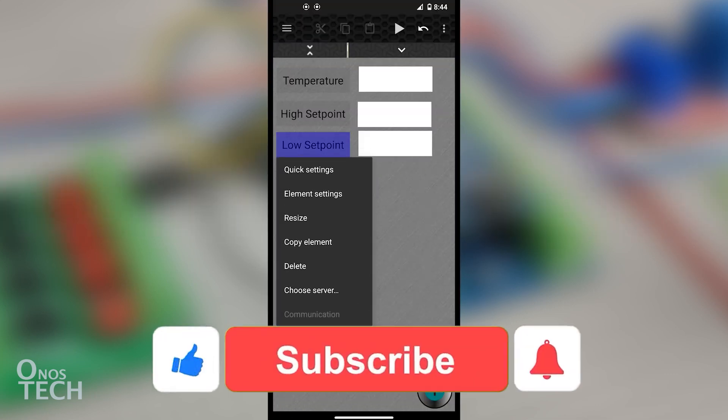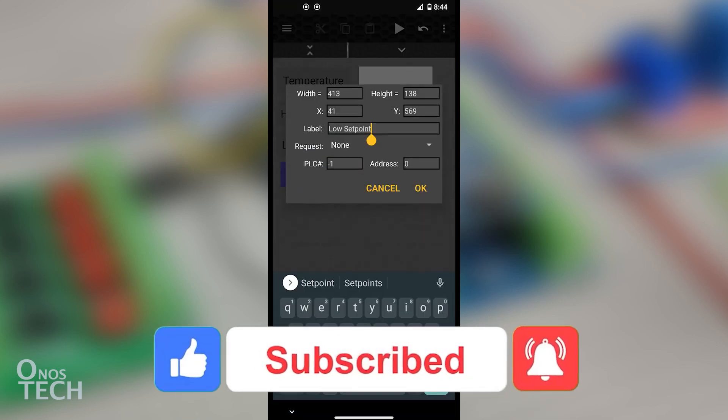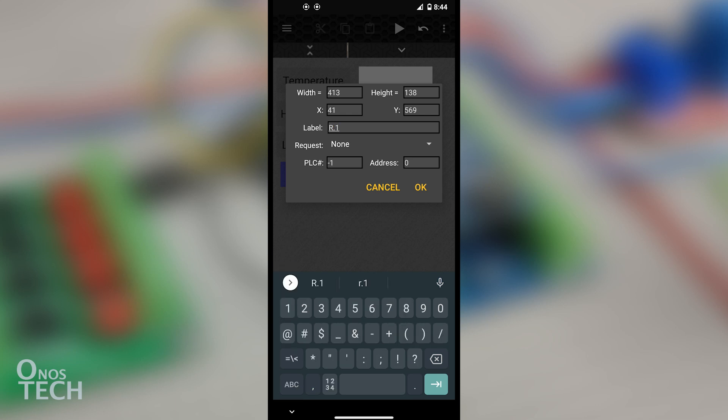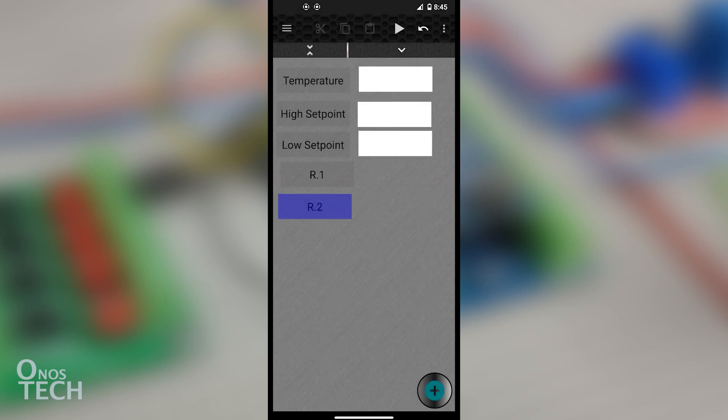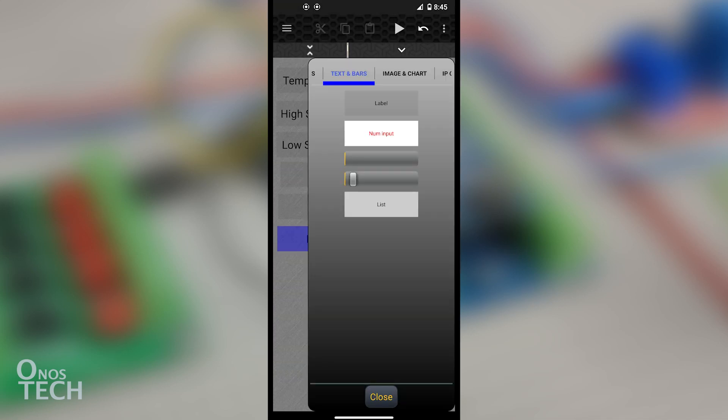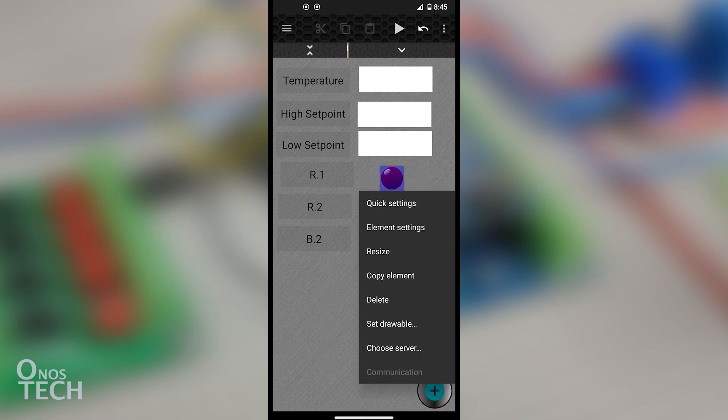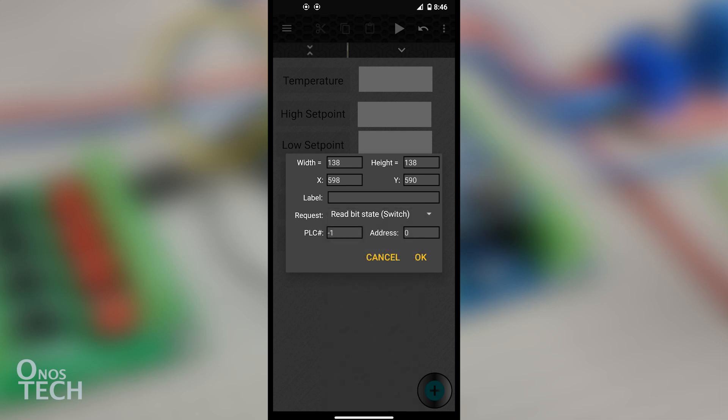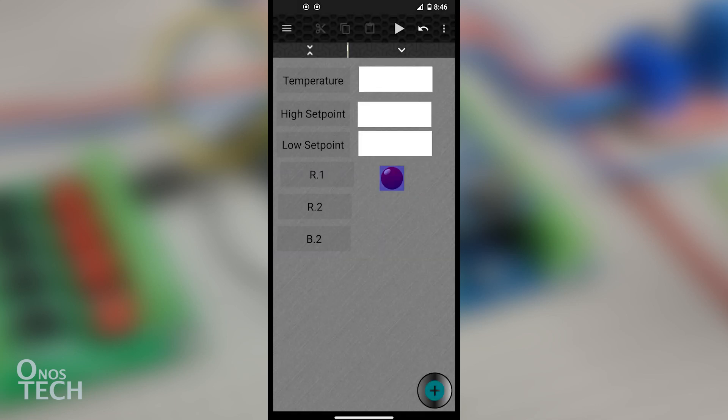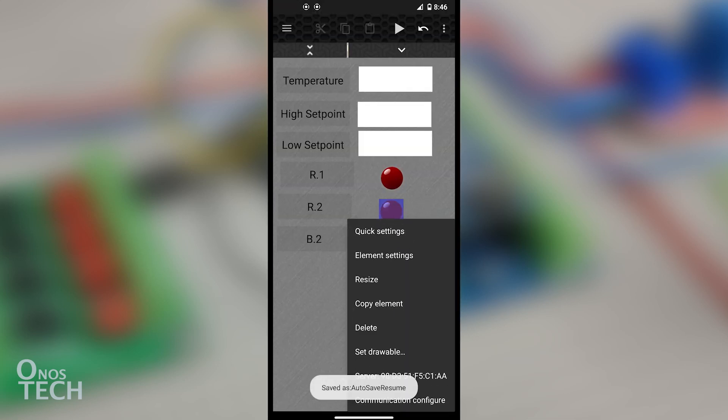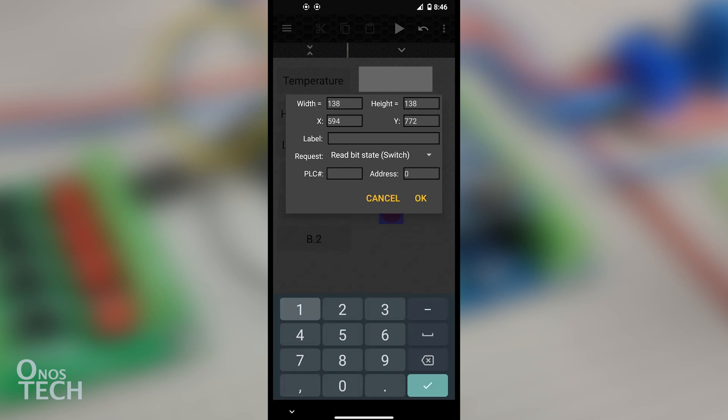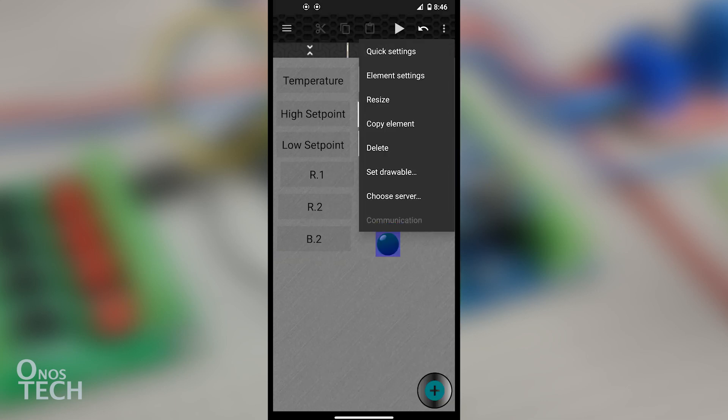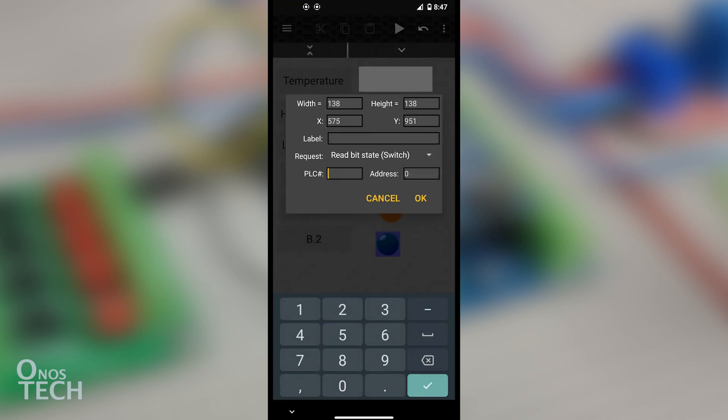To add digital input output elements, copy the Low Setpoint label and change it to R.1 from Quick Settings. Repeat to add labels for R.2 and B.2. Place a Red Indicator from the Switch tab before R.1, choose the HC05 server, and set the Request to Read Bit State Switch with PLC number 1 and address 0. Place an Orange Indicator before R.2 with address 1, and a Green Indicator before B.2 with address 129.